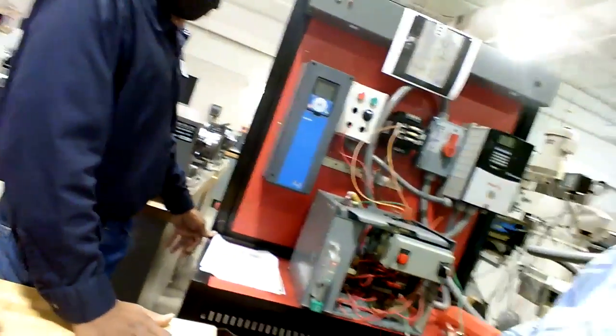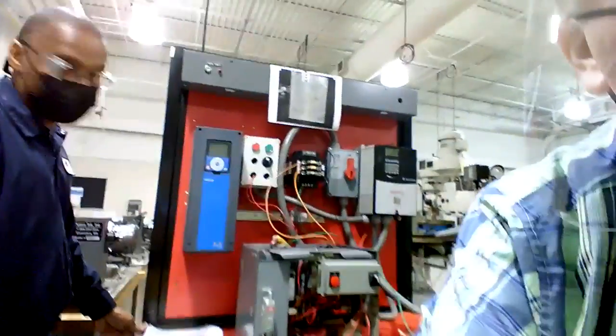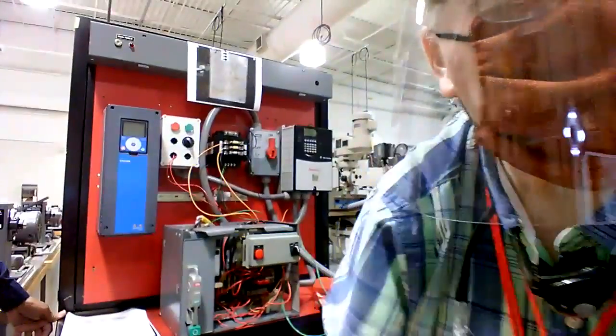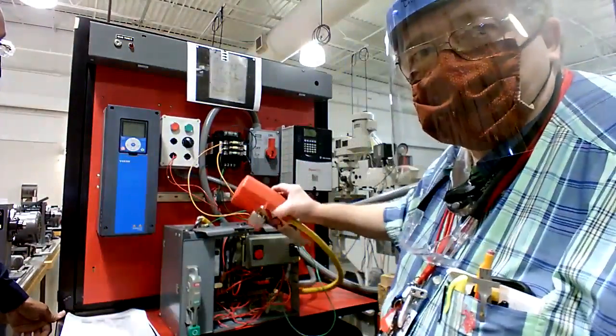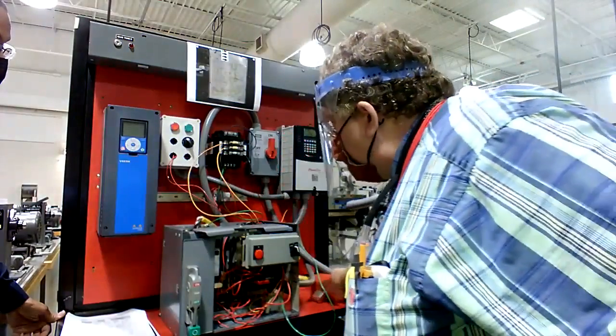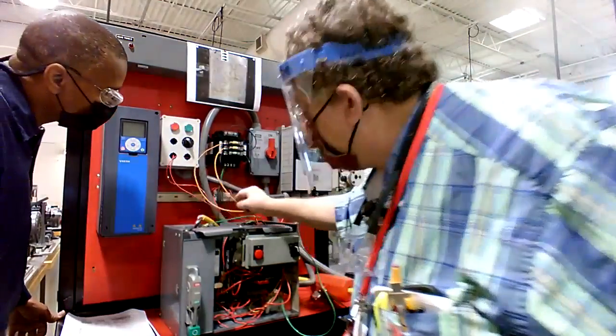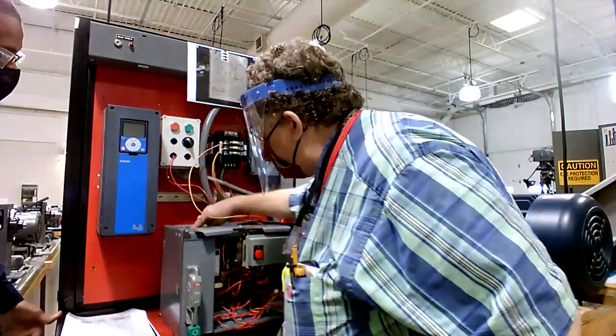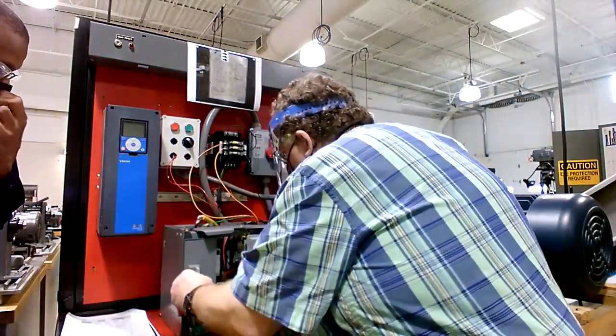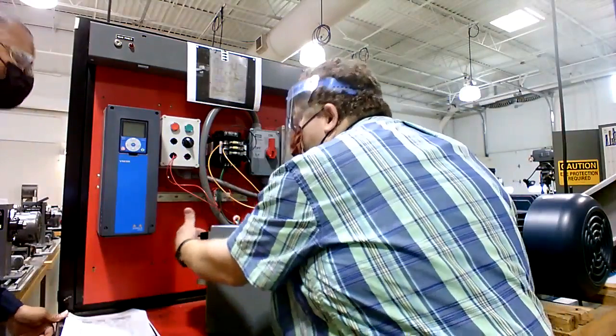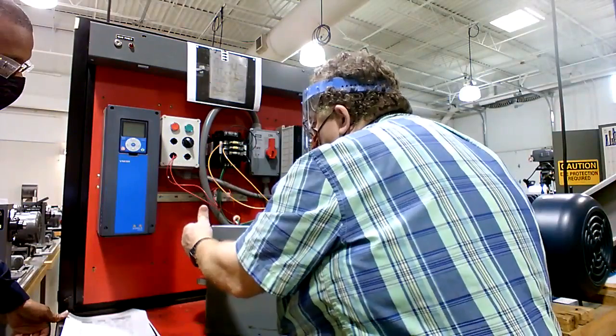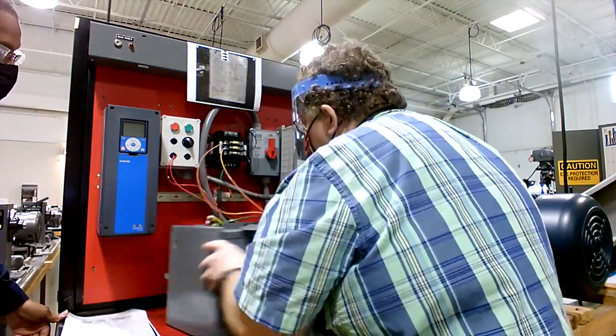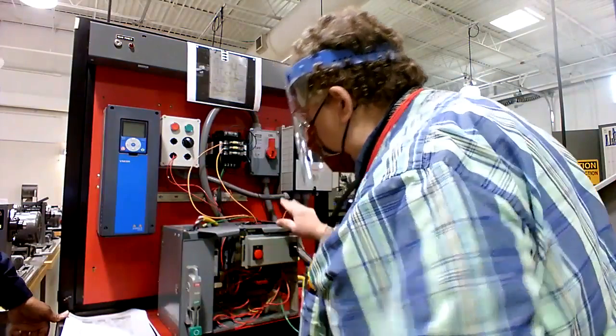Right now, what we have here is a lockout device, and we have a short pigtail that goes into the top of the bucket, and it's bringing the 480 straight in instead of going in through the rear like it normally would with the stab. It goes into the MCC structure. And those are locked out, so that's not a hazard right there. It goes straight in, and then it is just a normal bucket.